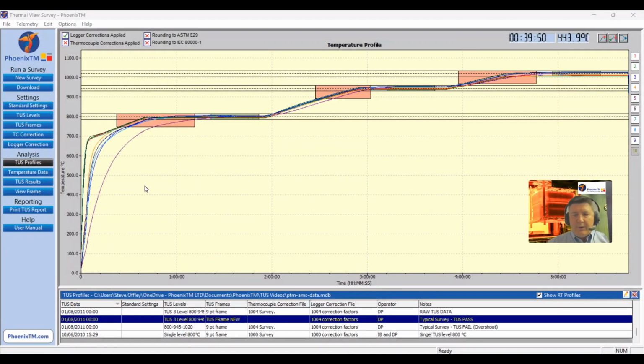So let us now investigate how we can apply a thermocouple correction factor file to a TUS run and also create a new file, a new thermocouple correction file from scratch. For the TUS run that we have visible on the software screen at the moment, you can see from the database that we have a logger correction factor file applied to the data, but no thermocouple correction file linked automatically. That's confirmed in the top left-hand corner here, where you've got a red cross against the thermocouple corrections applied. So this is a non-corrected TUS run in terms of thermocouple corrections.